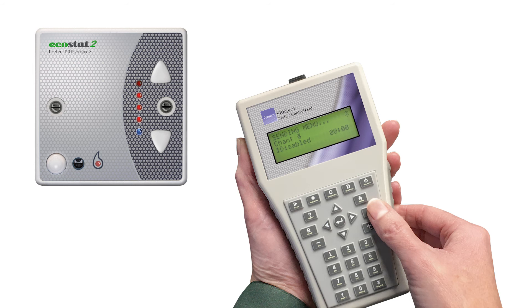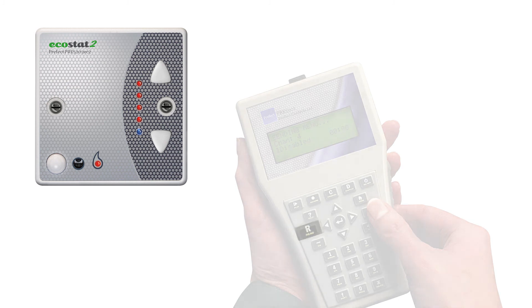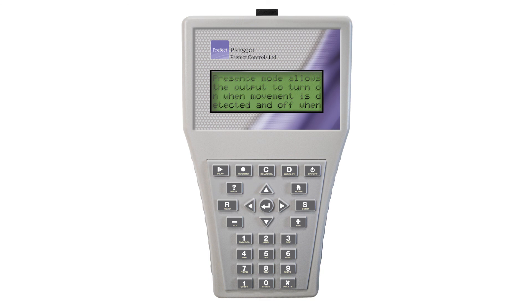If received successfully, the LEDs on the thermostat will flash. If you need to find out which settings are currently installed on the thermostat, press the read button — this will tell you the selected item. Press and hold the read button and all the settings will be downloaded to the handset. If two lines appear where you expect to see digits, this means the read was unsuccessful. Press read again, positioning the handset at a different angle or closer to the thermostat until values appear in the menu. If at any time you are unsure what each parameter signifies, press the help button and this will provide an explanation. The handset will remember all the settings as input, even when switched off. The only time they will be deleted is when the batteries are removed.